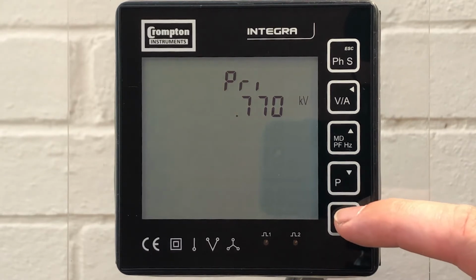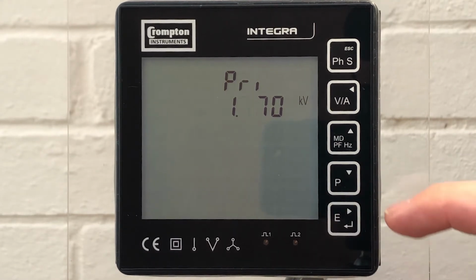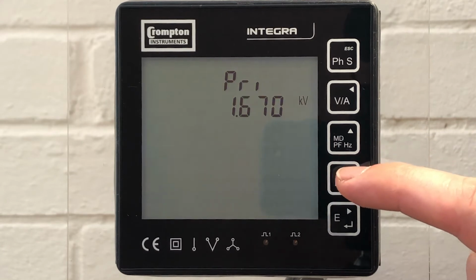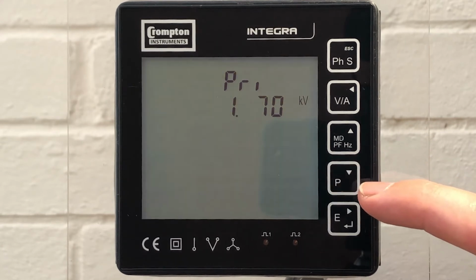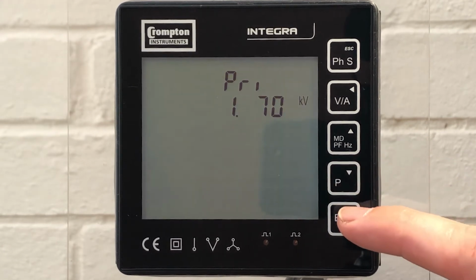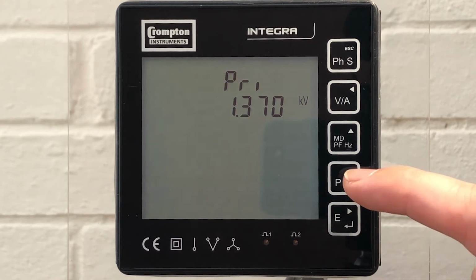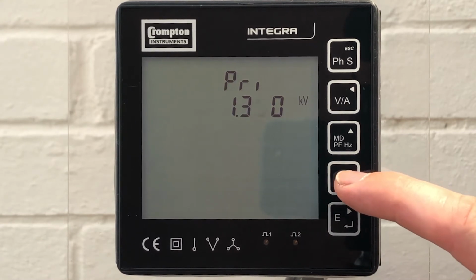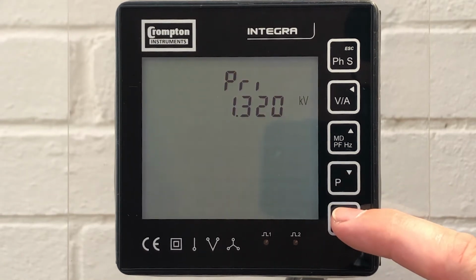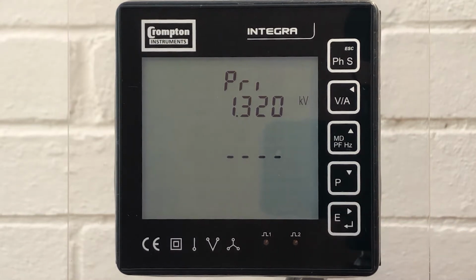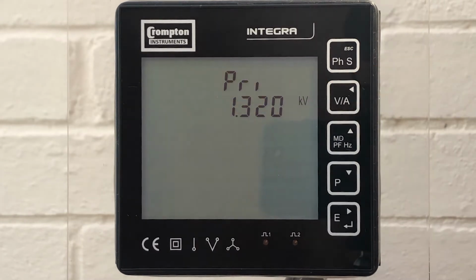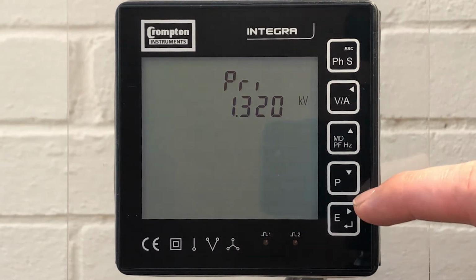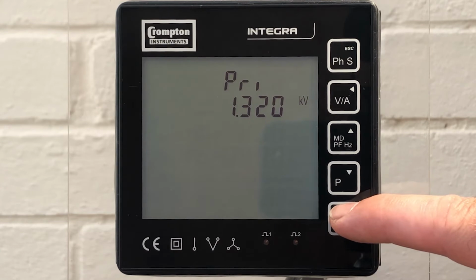Enter the number 1, press E to move on to the second character, change the second digit down to 3, the third character to 2, and press E and E once more to select 1320. Now you can see that we're saying 1.32 kV is not correct, so we need to change that to 132 and get the decimal point in the right place.